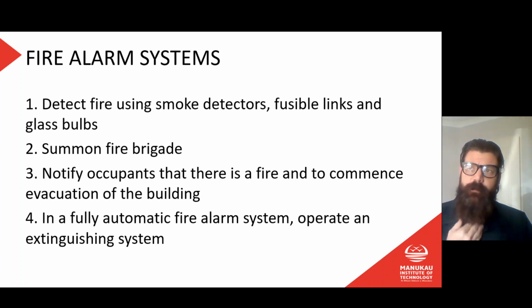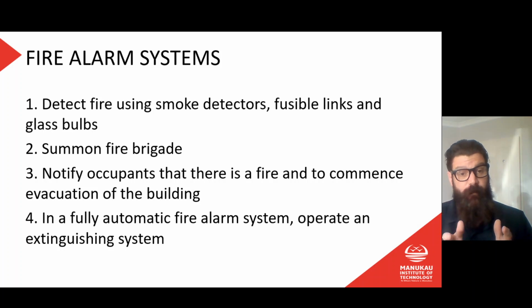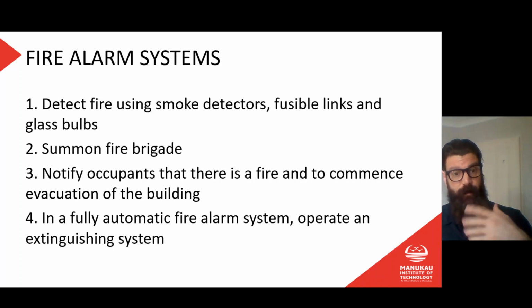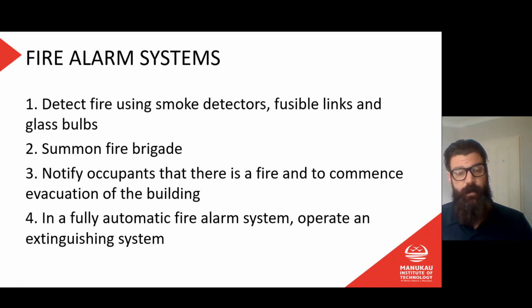Now it says it will summon the fire brigade. It won't always summon the fire brigade. There are certain situations where they must be connected to the fire brigade, and that's a communication system that's all of its own, by the way. The fire alarm system that's connected back to the fire brigade is generally totally separate from your other phone systems or anything like that on site, and it's connected directly to the fire brigade. So when that signal comes through, the fire brigade gets a notification, and they know exactly what building it is and all of that sort of stuff.